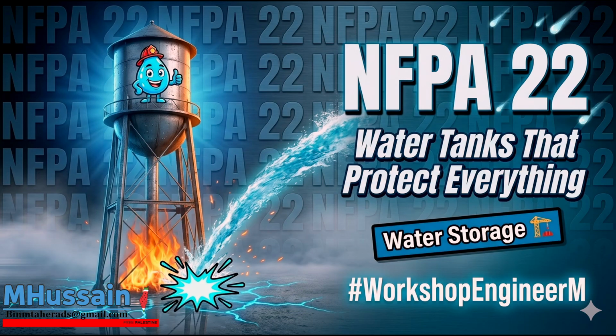Annex A and 7.1.4.2 details the physical calculations. You're utilizing Boyle's law, the principle that the pressure and volume of a gas have an inverse relationship. Right. You have to ensure that the volume of compressed air in the tank and the initial pressure it's placed under is sufficient to push every single required drop of water out of the tank, while still maintaining residual pressure. Exactly. You must maintain the necessary residual operating pressure at the highest sprinkler head in the building at the very end of the discharge cycle.